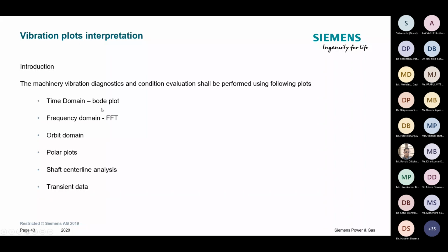Time domain means the vibrations plotted across time, to see how the vibration behaves and spot any abnormality. Based on experience, you come to know that these machines typically run with a certain level of vibration, and all of a sudden you see a jump or a step change. Then you know that at that particular time something happened. This can be seen from the waterfall plot or time domain plot.